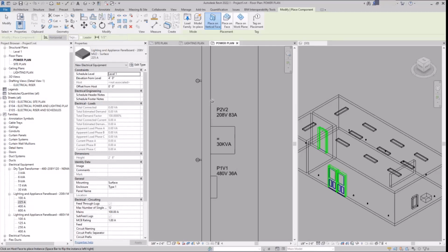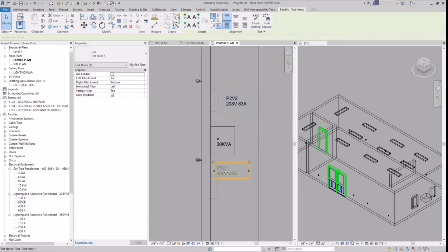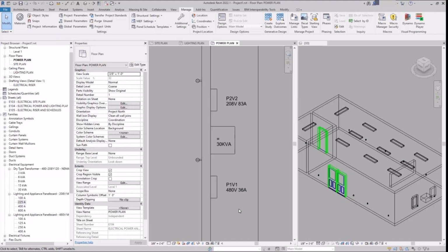225. And you're good. I'm assuming it's because of the load, like, what is it, the load percent? Like there's some kind of ratio that you have to be under. Like your panel has to be sized larger by a certain percentage than what your transformer can put out. Is that why? Close. Same concept, but instead of the panel board itself, it is actually the breakers. Gotcha.